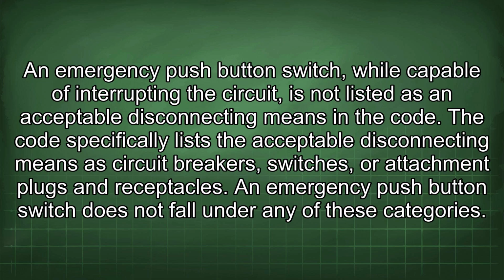An emergency push-button switch, while capable of interrupting the circuit, is not listed as an acceptable disconnecting means in the code. The code specifically lists the acceptable disconnecting means as circuit breakers, switches, or attachment plugs and receptacles. An emergency push-button switch does not fall under any of these categories.